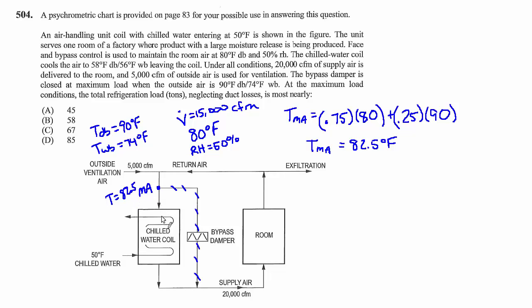If you're curious to know the humidity as well, you can do this same exercise on the psych chart by spotting these two states and then drawing a straight line between them, and then find 82.5 along that line and just look at the relative humidity curves. It turns out that even though it's a slightly higher temperature than the return air, because of the way the relative humidity curves are shaped, it actually still ends up being pretty close to 50%, so RH is about 50%. I don't know that we need that, but I was just curious. I always want to have a fully defined state, so I didn't want to write a temperature and not write something else in addition to it. That would make it seem that this state wasn't fully defined—it is fully defined at this point.